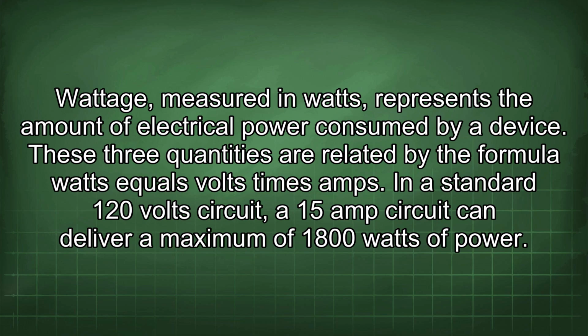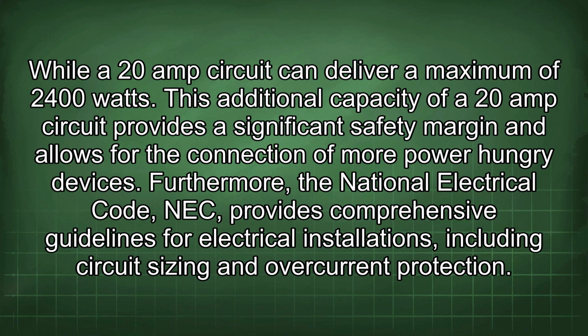In a standard 120 volts circuit, a 15-amp circuit can deliver a maximum of 1800 watts of power, while a 20-amp circuit can deliver a maximum of 2400 watts. This additional capacity of a 20-amp circuit provides a significant safety margin and allows for the connection of more power-hungry devices. Furthermore, the National Electrical Code (NEC) provides comprehensive guidelines for electrical installations, including circuit sizing and overcurrent protection.